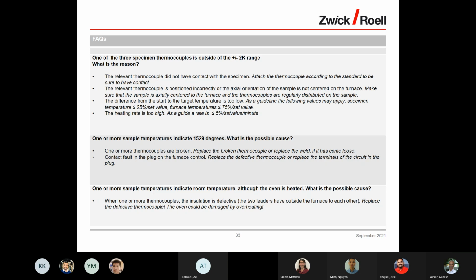One or more sample temperatures indicate room temperature, although the oven is heated. What is the possible cause? One or more thermocouples in the insulation are defective. Replace the defective thermocouple. The oven could be damaged by overheating. Be careful.